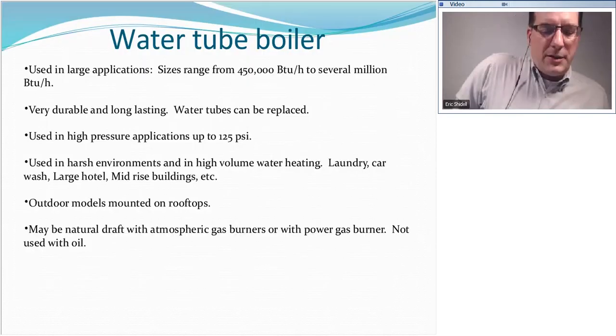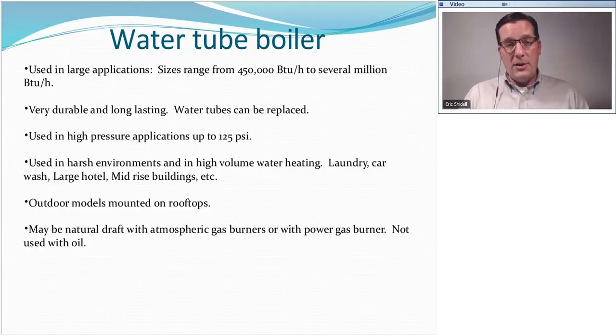Water tube boilers are used primarily in large applications. Sizes range from the small end is 450,000 BTU, and they top out at several million BTU per hour. They are incredibly durable, very long-lasting, and the water tubes can be replaced. Changing out a water tube boiler isn't something that happens every day. It's more likely they're going to be replaced. And be aware, too, that when a water tube boiler gets replaced, very frequently another brand new water tube boiler is going to go into that same application.